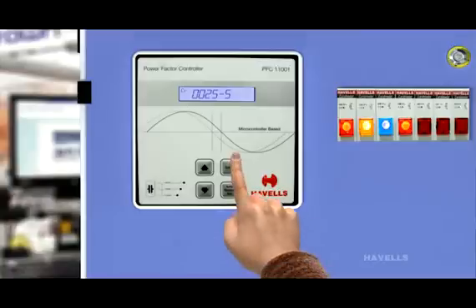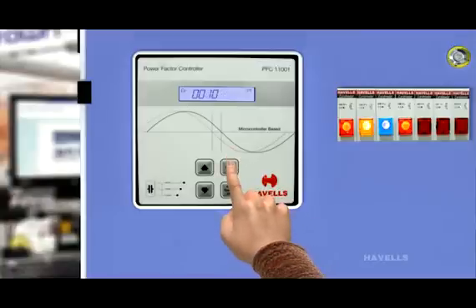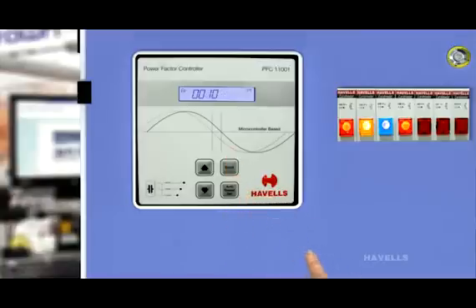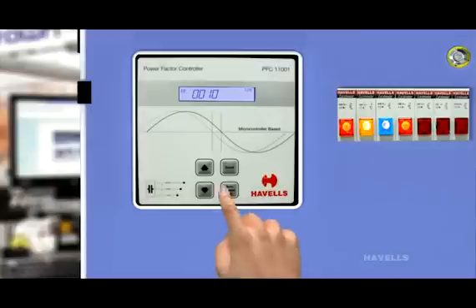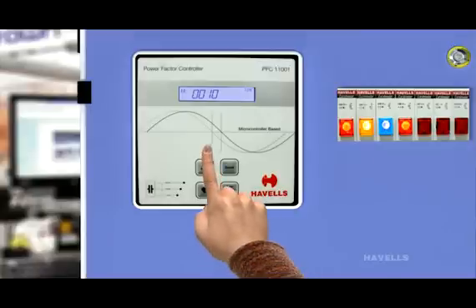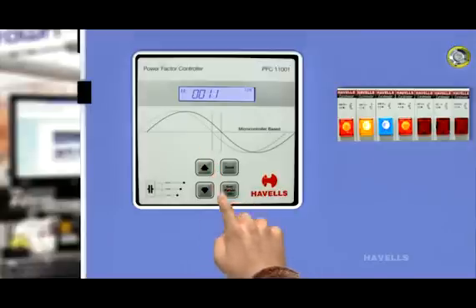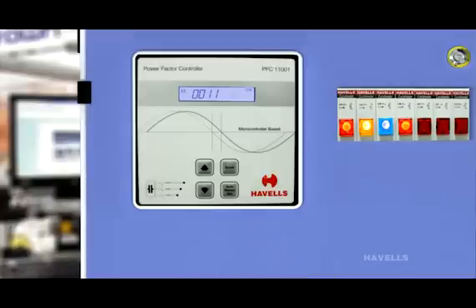Press scroll switch again. Controller shows the switching time of capacitor bank on LCD, which is 10 seconds. Through up and down switch, switching time can vary from 2 seconds to 1800 seconds.